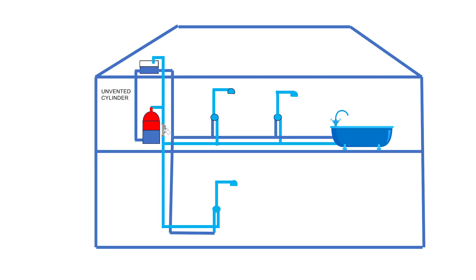A typical shower or tap requires two thirds hot mixed with one third cold to achieve the desired temperature. A single SP2B boosting the hot only will give four times the pressure and double the flow for a typical upstairs shower.